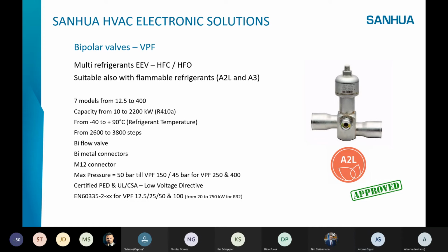So yeah, they are certified PED, ULCSA, and low voltage directive. They are also certified for flammable refrigerant via the EN 60335-2 for the first 4 sizes. So it's corresponding to 750 kilowatt for R32 for one circuit. So it's already a huge unit.